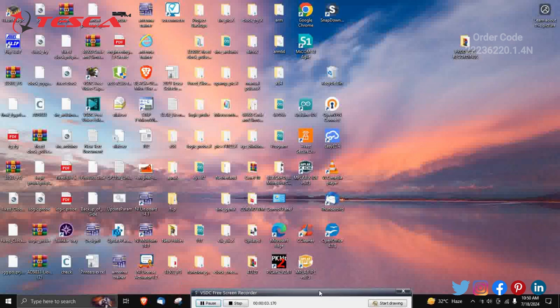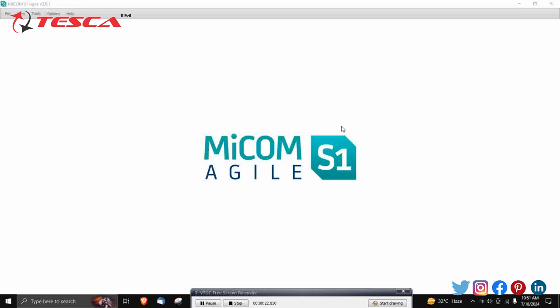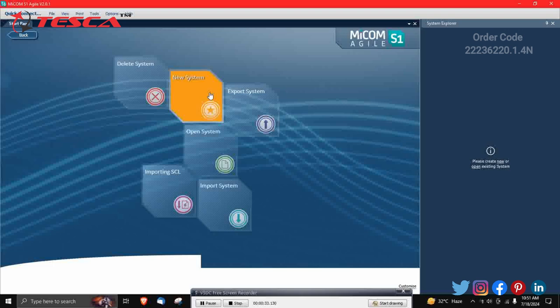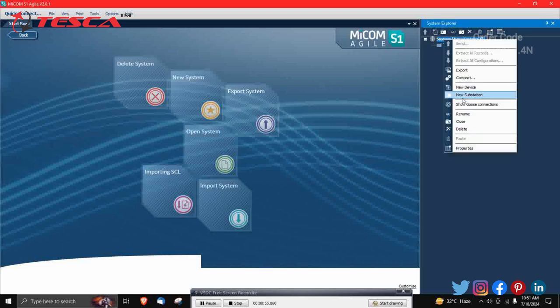Now we will move to the software part of the directional and non-directional overcurrent relay trainer. First, go to the MiCOM S1 Agile software and double-click to open it — it will take a few seconds. Click on System Explorer, then click on New System, name it anything (for example, 'New System 2'), optionally change the path, and click OK. Then right-click on the system and click on New Substation.